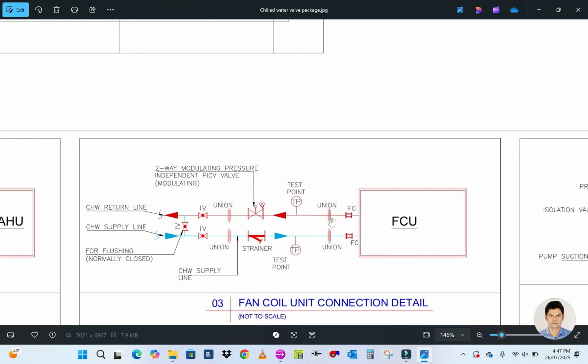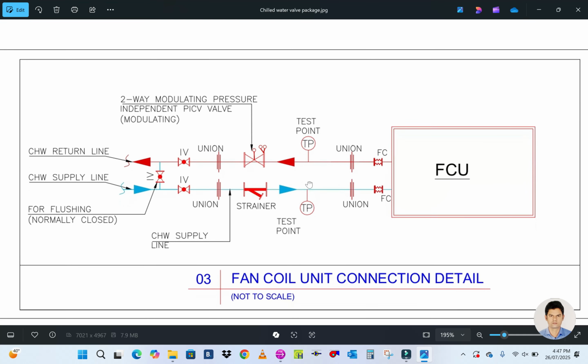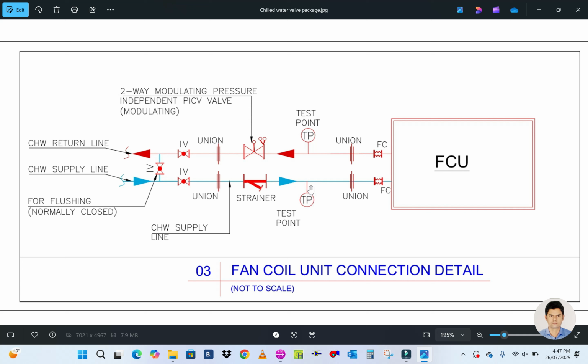Next is the union. The union is not part of the valve package, and the second one is the test point. The test point is also not part of the valve package, because the test point is installed on the surface of the pipe. Next, you can see here in the supply line, first comes the isolation valve. The isolation valve is nothing but the gate valve. You can use a gate valve or a butterfly valve, any one of them, as per the space availability.